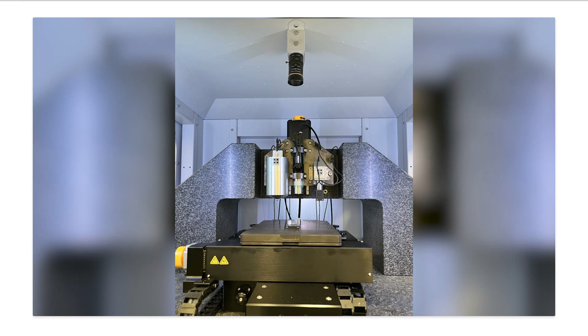This is a multi-purpose sample chuck with various mounting options. So we have magnet locations, vacuum rings of various sizes, screw locations for mounting sample mounts, and so on. Here we have our application scientist mounting a high entropy alloy sample onto a platen and bolting it securely to the stage. We use a top-down navcam, which is mounted on the inside of the top enclosure. The microscope optics are good for navigating around a particular sample for locating areas of interest for testing, and the magnification is optimized for looking at the overall stage setup with multiple samples.